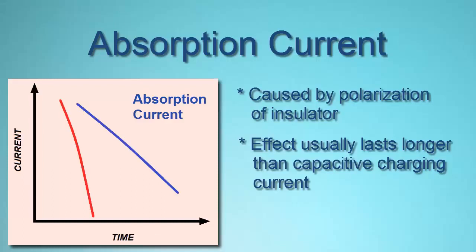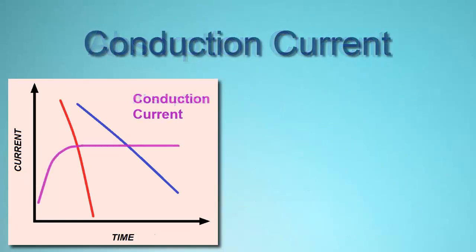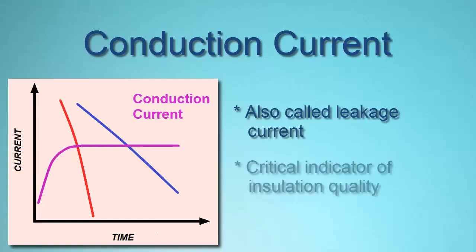The length of time it takes for absorption current to fall off can be affected by moisture or other contaminants in the insulation material. Therefore, absorption current is an important indicator of insulation integrity. Conduction current, often called leakage current, is the steady current present both through and over the insulation. This is a critical measurement, since an increase in conduction current over time is likely an indication of deteriorating or damaged insulation.